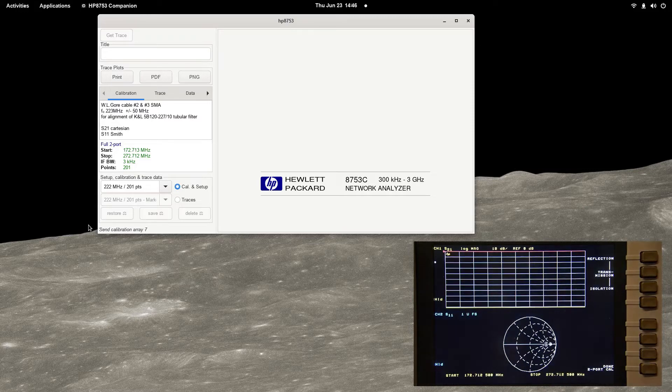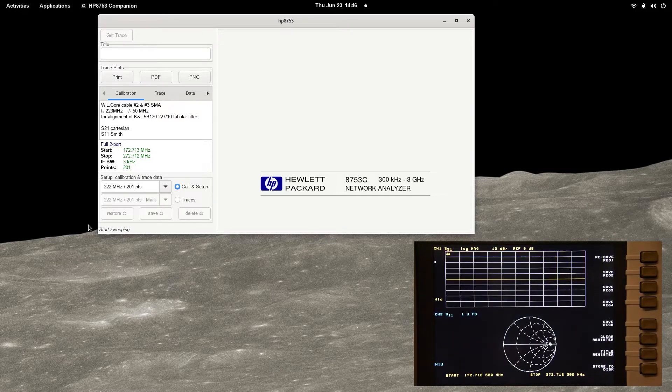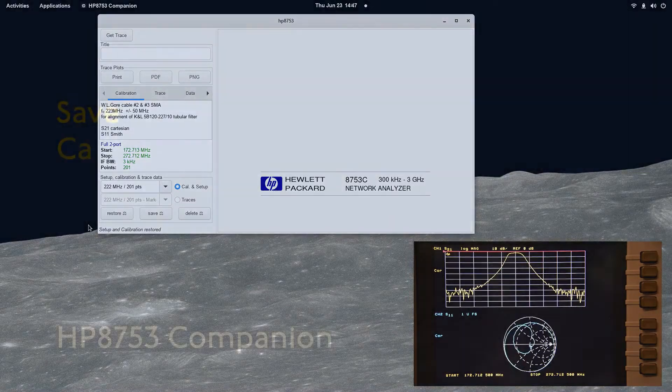The type of calibration, number of sample points and whether the source channels are coupled alter the amount of data that is sent.